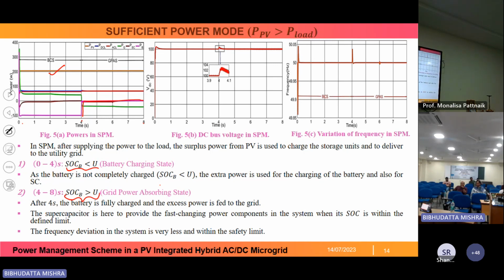Previously the grid power is positive, meaning the grid is supplying power to the system. After 4 seconds, when the battery is completely charged, the grid is taking power from the system, so this power is now negative.